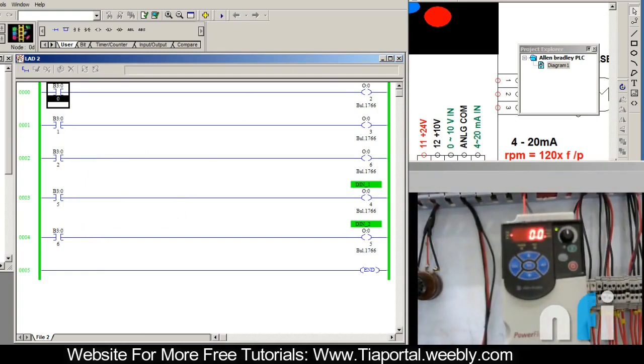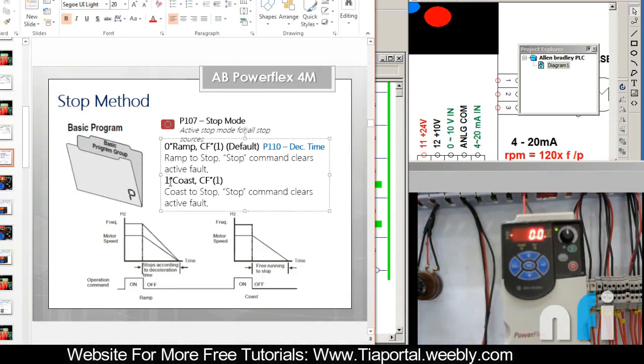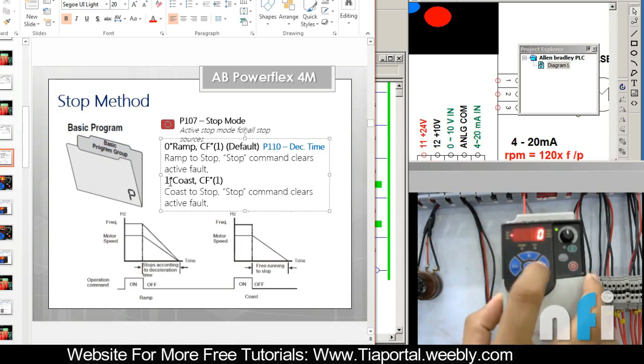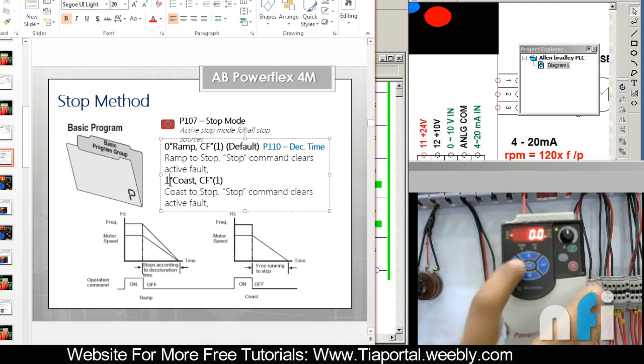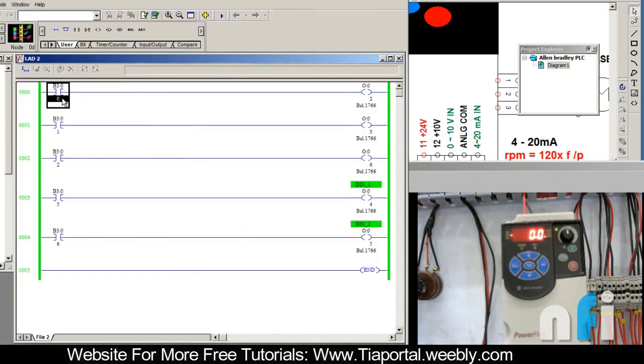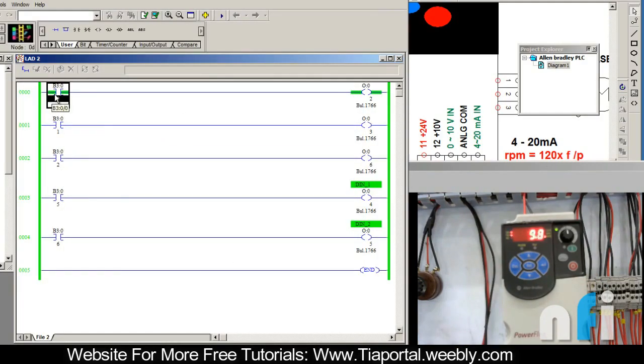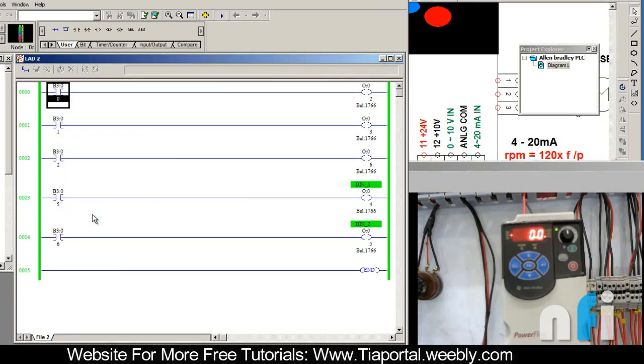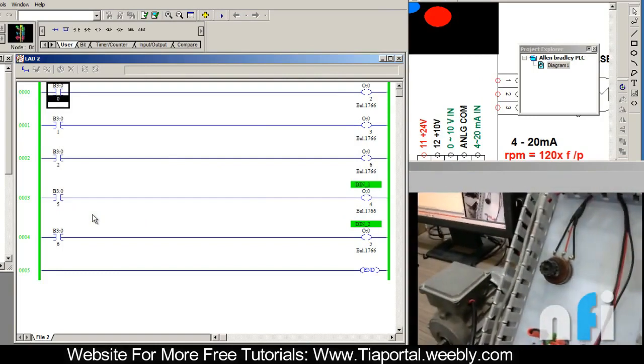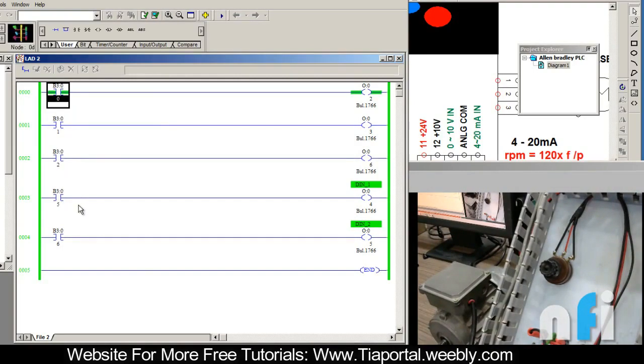Next is coast stop. When you go to coast stop, this is parameter 107, this will enable the motor to run by its own inertia. So when I start the drive here again, let's go to 22.3. When I stop it, the motor will stop by its own inertia.